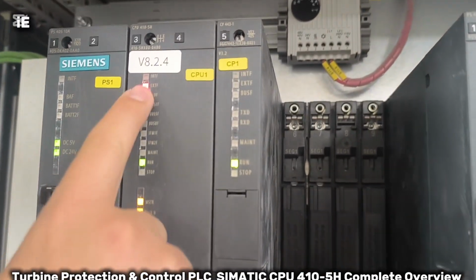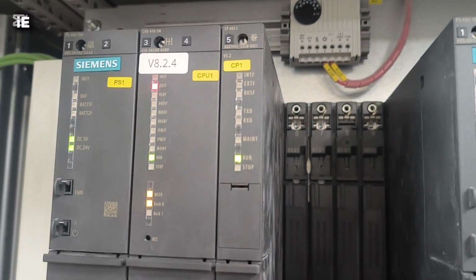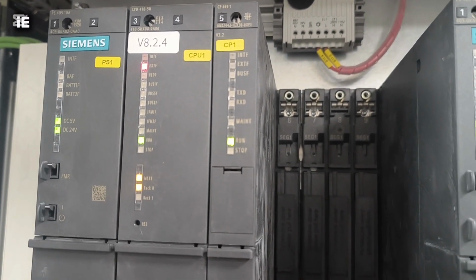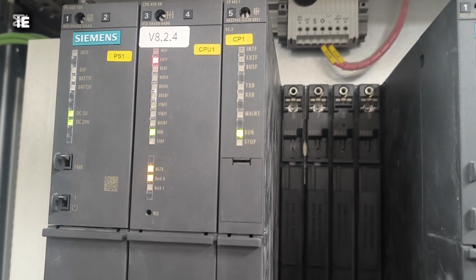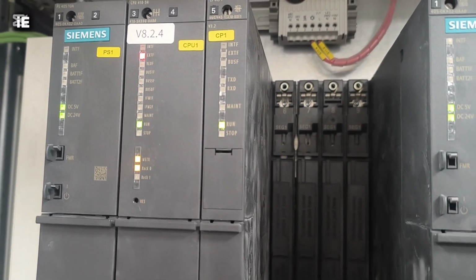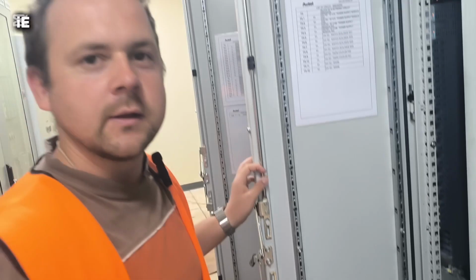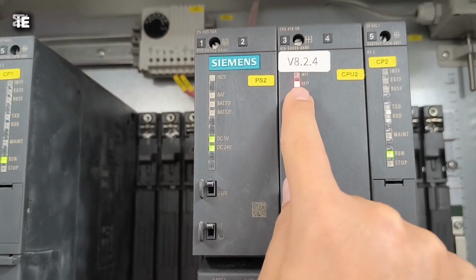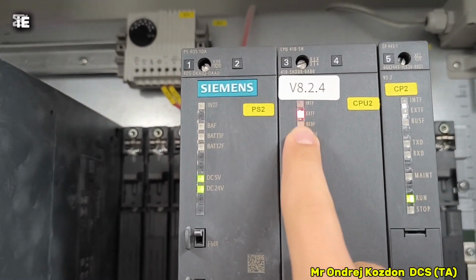Then we have external fail, and this is when using diagnostic of the I/O cards. So for example, wire break or short circuit of some analog input, digital input, then you have external fail, and this will be also shown in the operator station. About the external fail, we will talk later more.